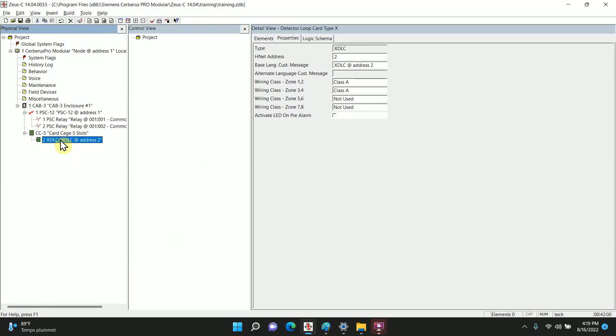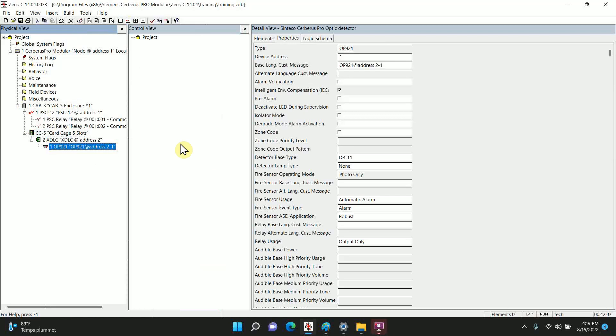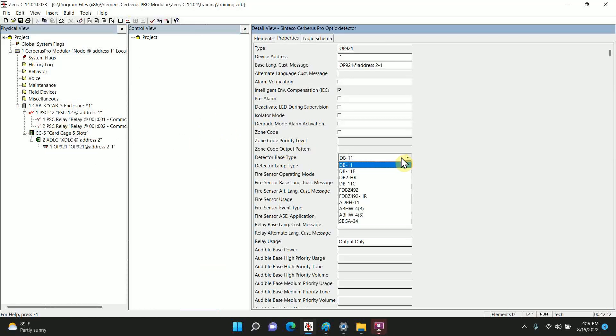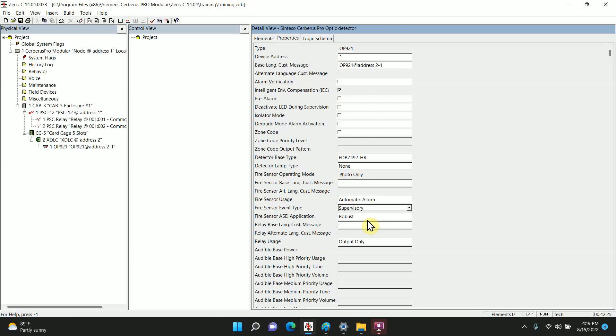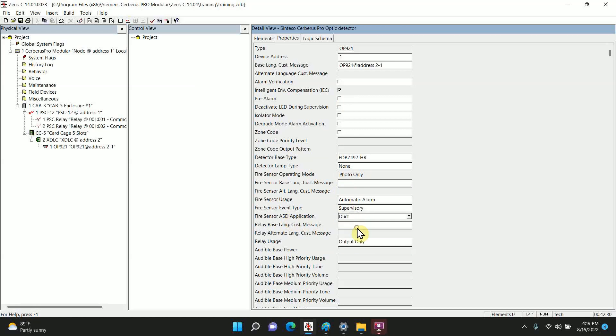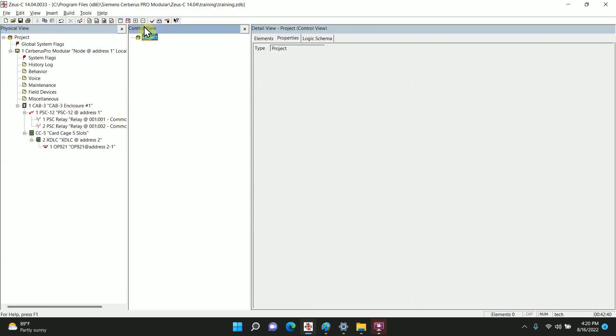We're looking for the OP921. Click on OP921, see all the settings here. Detector base type, again I said it's FDBZ492HR. And we're using this as a supervisory, so on fire sensor event type we're going to make that supervisory. On the ASD application, I'm going to switch this to duct because it's a duct detector type. All right, and with that it's going to add to the hardware tree. How do you make it work?